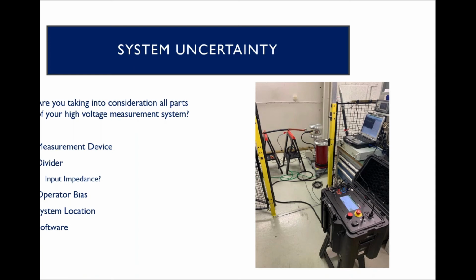Most dividers also have a specific level of input impedance required of the measurement device. If your measurement device does not have the proper input impedance, this could lead to a very substantial error in your system. In addition, the input impedances of the measurement device are typically also specified with a range of values, which could even skew your measurements more. This is why it really is important to calibrate your divider and your measurement device as a system pair to ensure that everything's being taken into consideration.